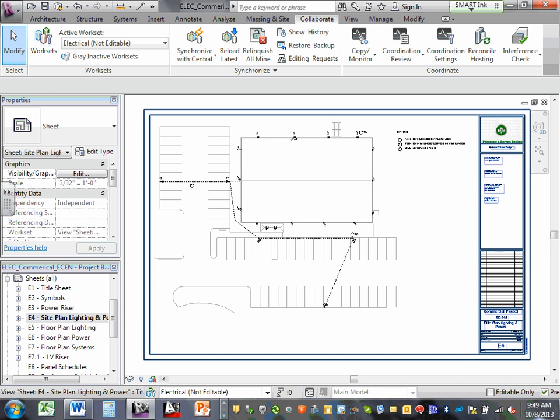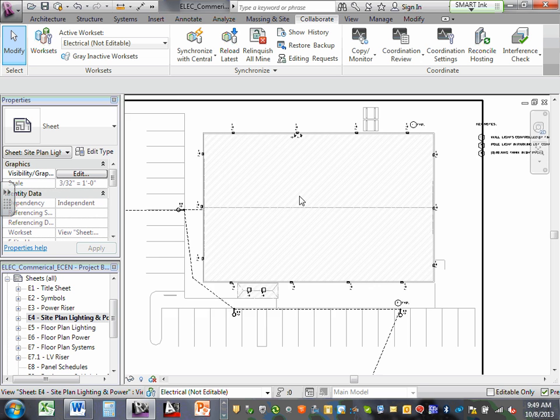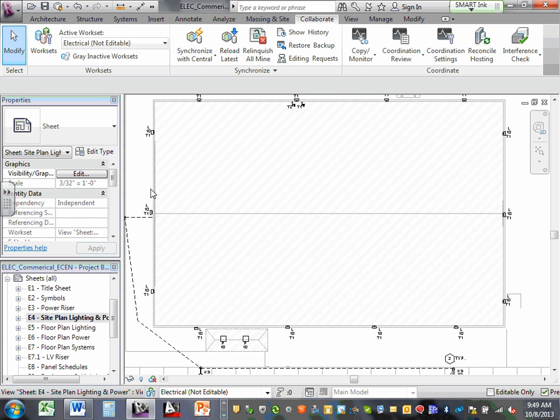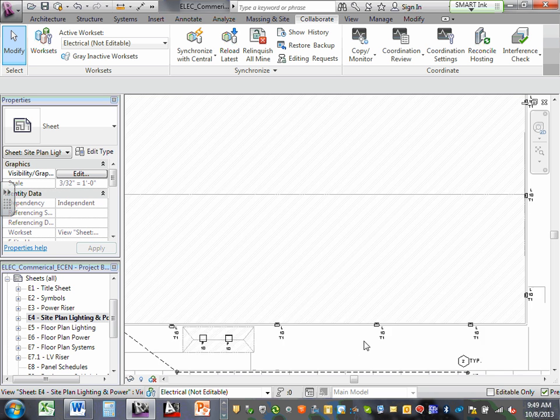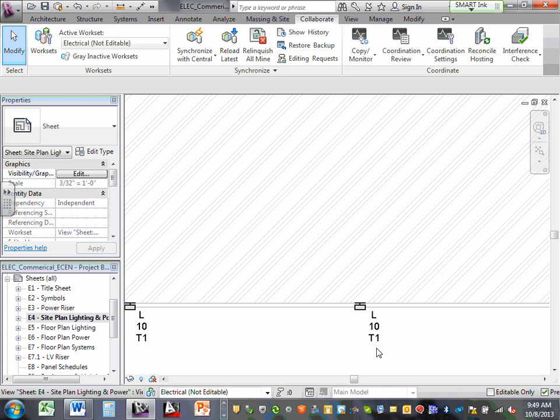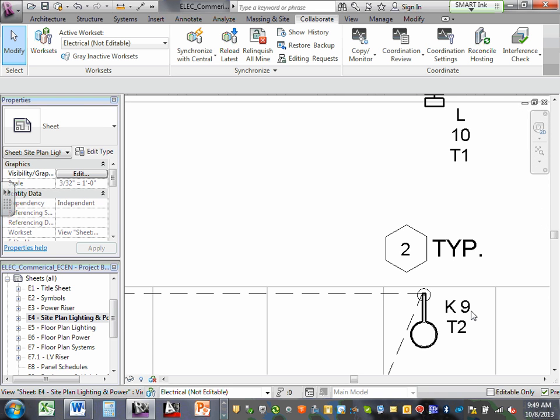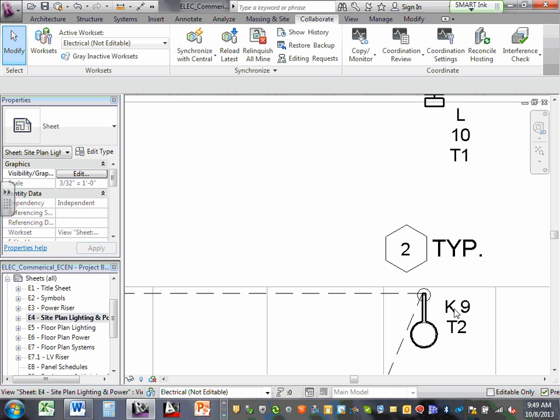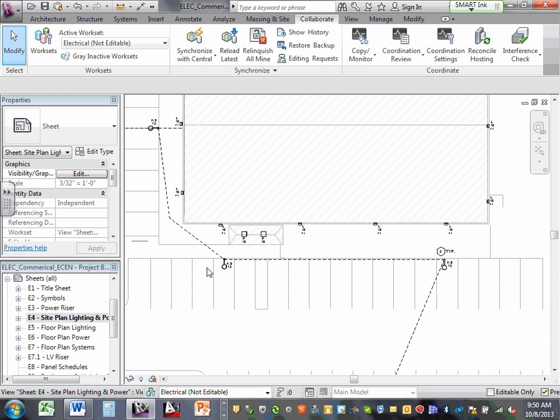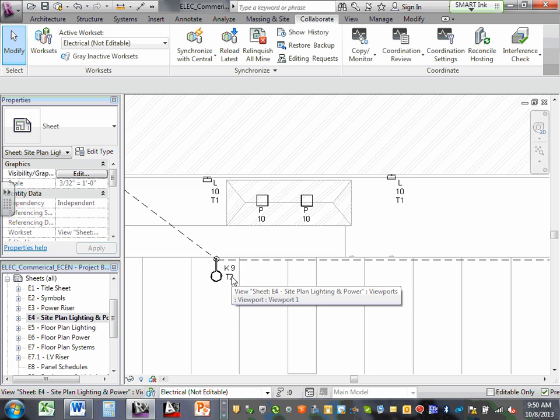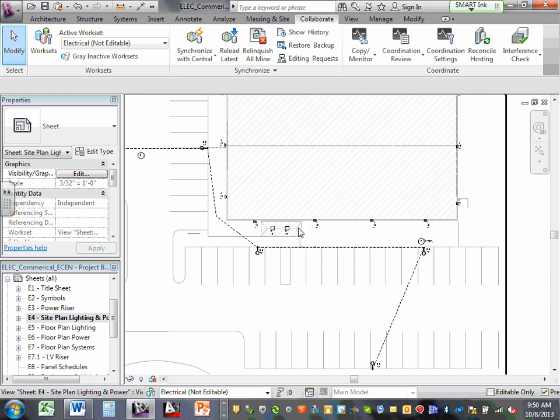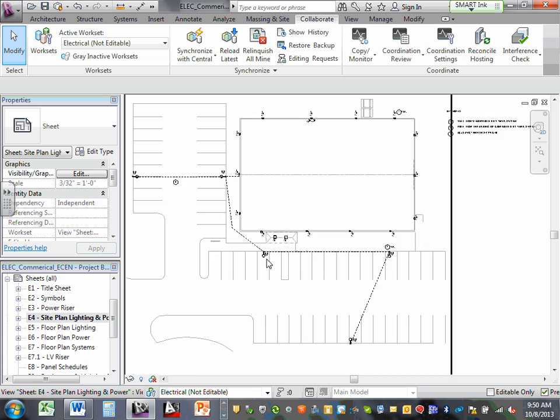When you go to the site plan, here's my building — the roof — and here's the light sitting right next to the building. All the lights are labeled: fixture type L, circuit 10, Timer 1 will control it. Here's my parking lot light — it's K9, meaning fixture K, circuit 9, Timer 2 is going to control it — and that label is typical for all of them.